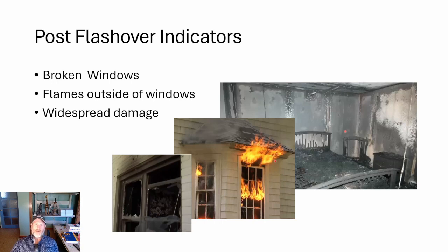I wanted to talk about one issue here while we're on this page, and that has to do with this bottom image, this image of these broken windows. I heard a story once. A friend was called in after the fact to analyze a fire that occurred at a summer camp, and it occurred in the wintertime. So they were going back and doing the forensics, and one of the fire protection engineers called upon to do this analysis, strictly based on photographs, concluded that there was some kind of an explosion involved, so likely an arson-related event.